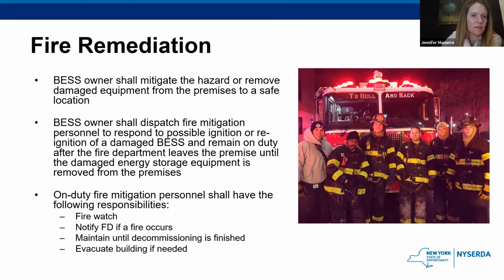Okay, another super fun code requirement, I like this one a lot, is fire remediation. So this essentially says that if an incident does occur in the system, the owner is responsible for not just removing the damaged equipment from the premises to a safe location after the first responders have done their thing, but the owner is also required to dispatch fire mitigation personnel to essentially babysit the fire, or babysit the system rather, and relieve the fire department of its duties.